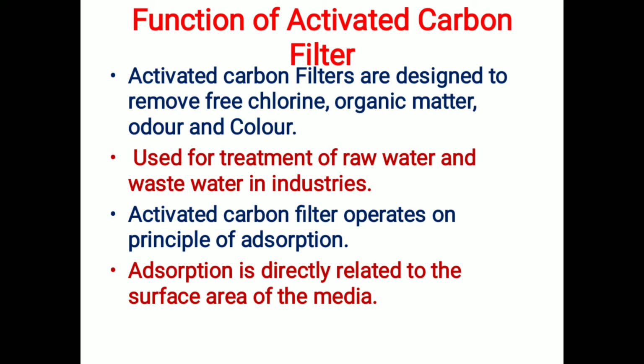Now we'll see the function and application of the activated carbon filter. Activated carbon filters are designed for removing free chlorine present in water. We use chlorine as a disinfectant in water. After killing bacteria and microorganisms, some chlorine remains in free form in water. So for removal of this free chlorine, we use an activated carbon filter.